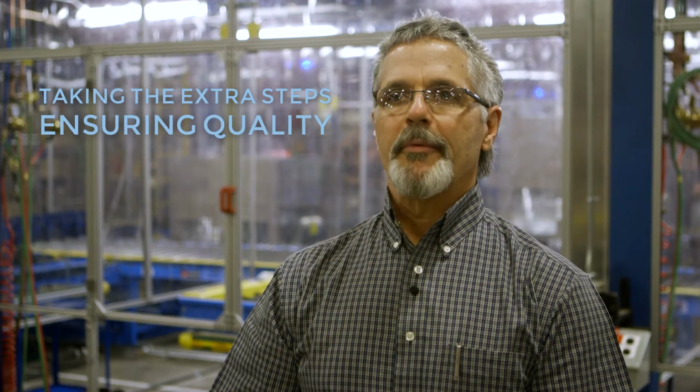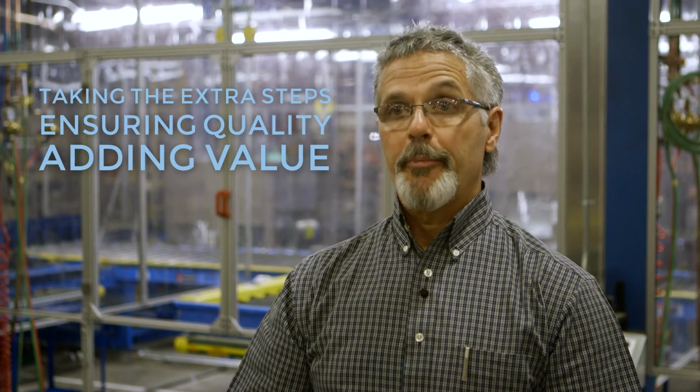Everybody has to run the standard AHRI rating test to sell the product, but hopefully we're taking the extra step to give the customer added value through transit tests and shipping tests, to make sure that any copper or component failures occur here and we can design those resonances or frequencies out of the product. Also doing rain tests, to make sure we don't have any water being drawn into the cabinet. And we're doing sound tests, trying to get the dB of the compressor and the outdoor fan down to a comfortable level.